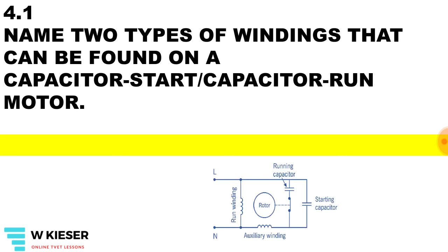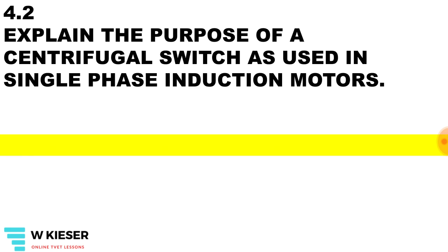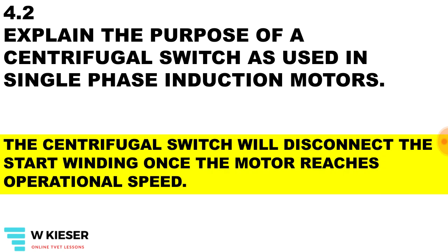We have two types of windings found on capacitor start and capacitor run induction motors: the start winding and the run winding. Explain the purpose of a centrifugal switch as used in single-phase induction motors. The centrifugal switch will disconnect the start winding once the motor reaches operational speed.